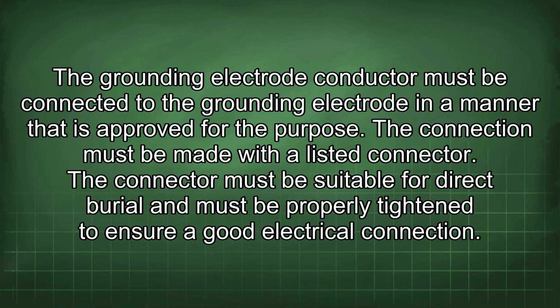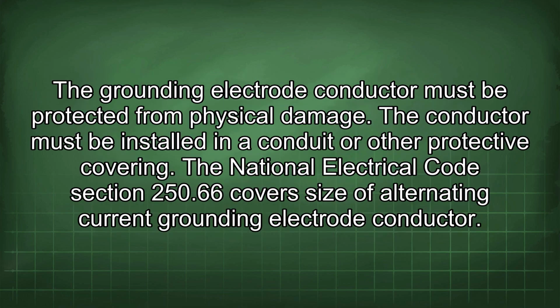The grounding electrode conductor must be connected to the grounding electrode in a manner that is approved for the purpose. The connection must be made with a listed connector. The connector must be suitable for direct burial and must be properly tightened to ensure a good electrical connection. The grounding electrode conductor must be protected from physical damage. The conductor must be installed in a conduit or other protective covering.